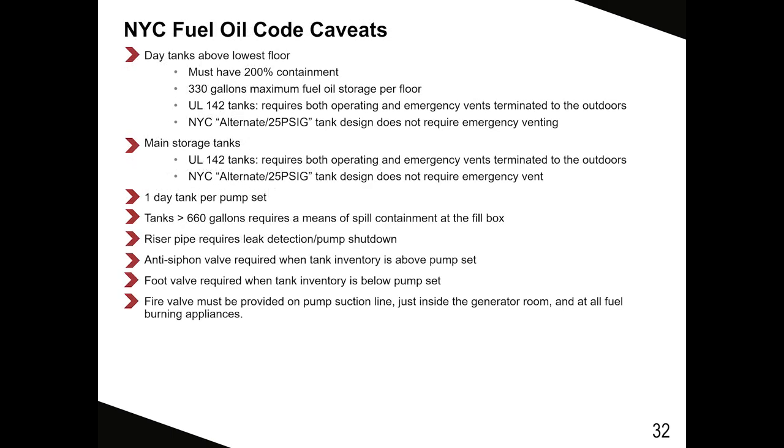New York City fuel oil code caveats. For day tanks above the lowest floor, you must have 200% containment. Your maximum is 330 gallons of storage per floor.